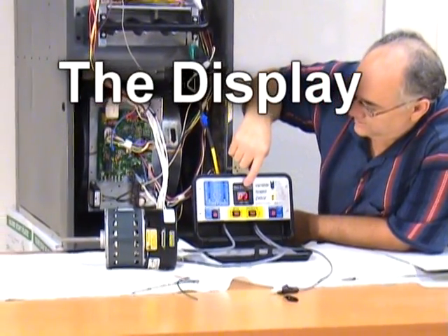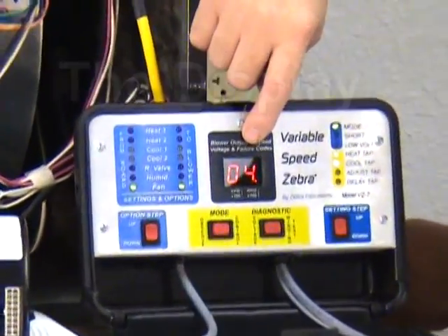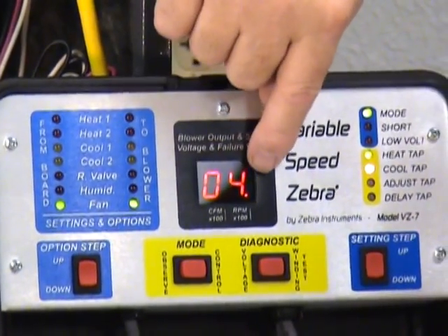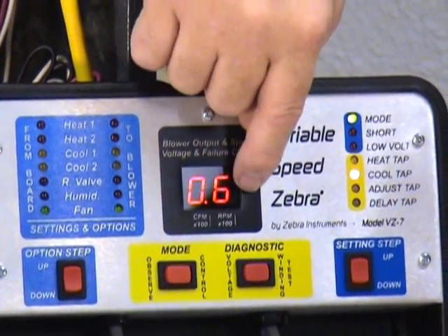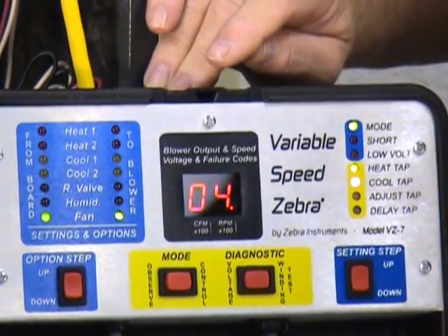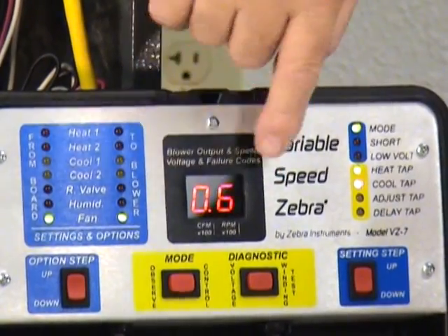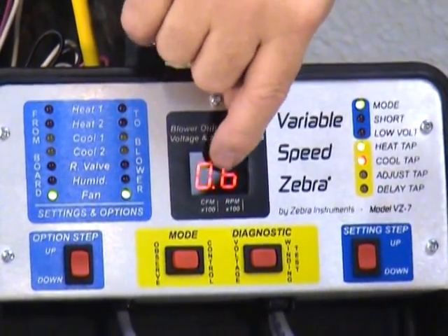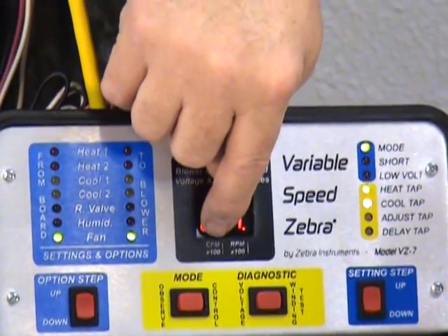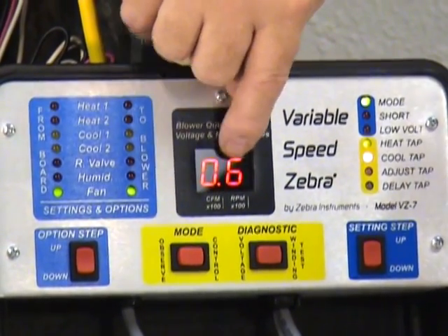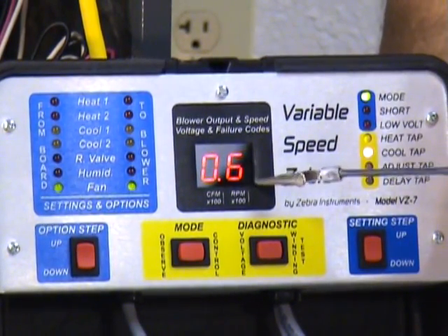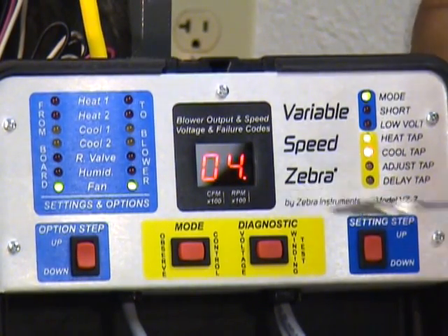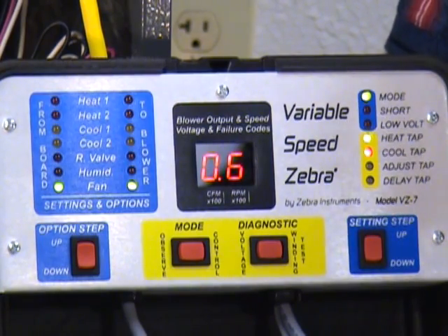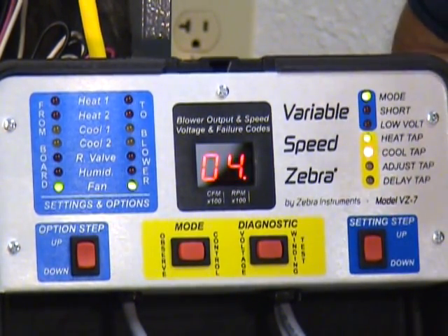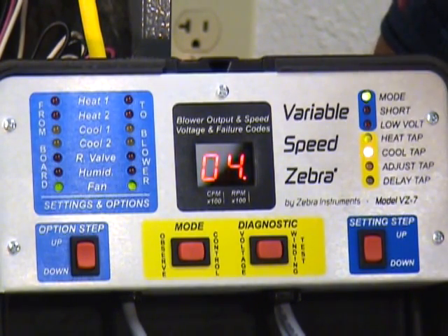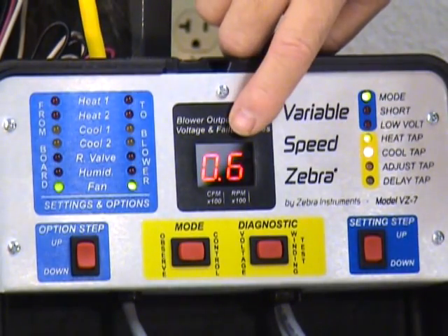Let's focus down here on our display. Get really tight on that. Okay. As you look at the display, what we normally call a decimal point, you'll see moves back and forth about every 5 seconds. It's not a decimal point, folks. It's simply a light to tell you which display it's displaying. If that light is above the letters CFM, then it's displaying CFM, and you've got to multiply it by 100. If that light moves over to this side, as it will right now, and it's above the letters RPM, it's displaying the RPM of the motor. And it'll change back and forth every 5 seconds or so to tell you what that motor's doing. It normally takes about 30 seconds after the motor reaches a speed before you can count on that being an accurate display.